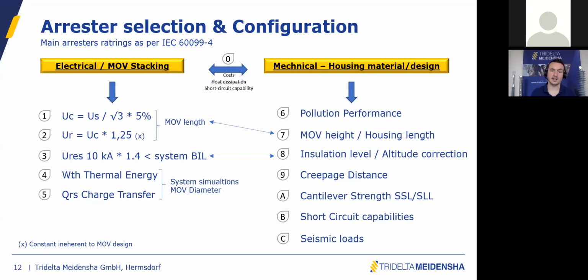This constant is actually inherent to the MOV design. It has to do with the metal oxide technology. It's the ratio between the continuous operating voltage that the MOV can withstand over 30 years, 50 years over the service life, and its capability to withstand a temporary overvoltage for 10 seconds with prior duty. I'm going to give some more details afterwards. But basically, the ratio is fixed. It has to do with the MOV technology.